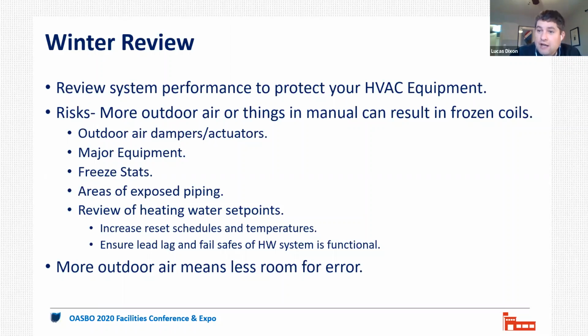When we're bringing in more outdoor air, we also want to think about the sequences of how these units start up. Often freeze stats get tripped right upon startup because the coil hasn't heated up enough. Maybe the warm air on your return side has cooled down, and it's not really pulling the warmest air from the space. So you get that situation where a unit kicks on and then immediately trips on the freeze stat.